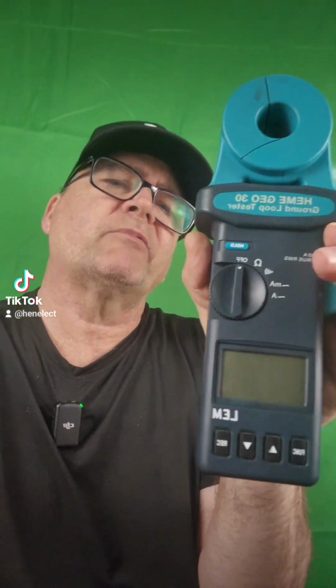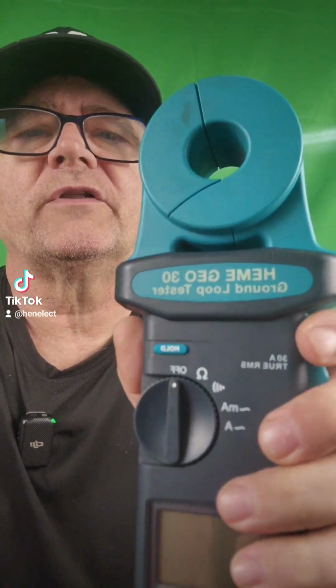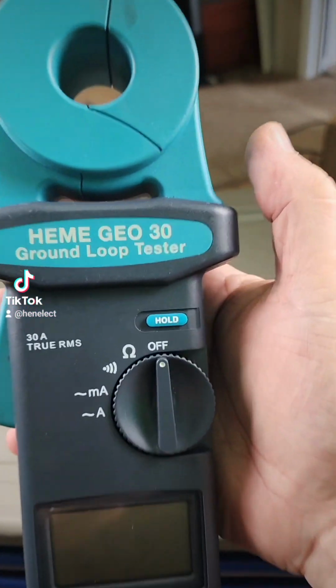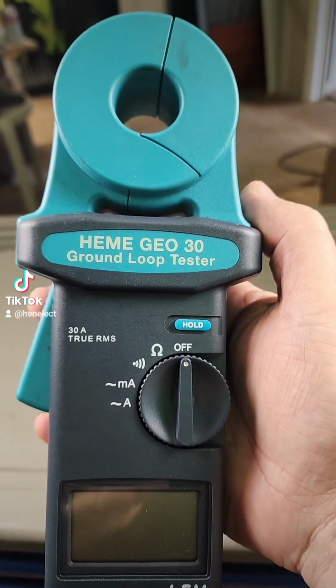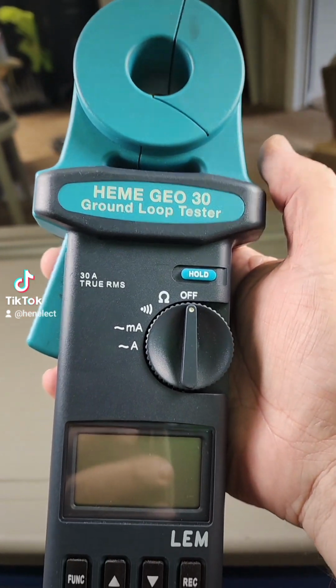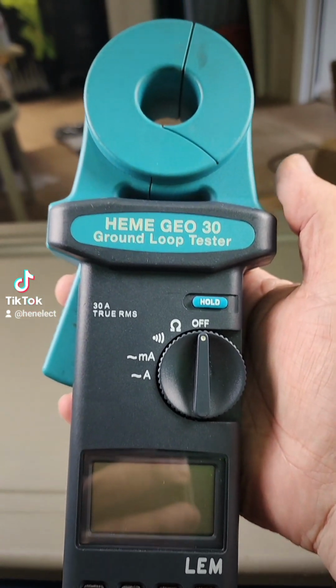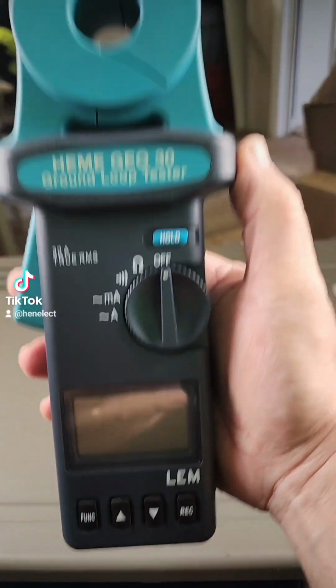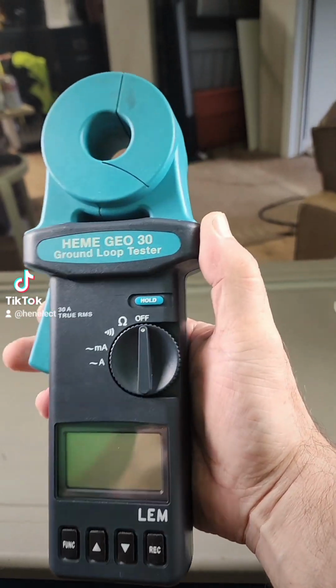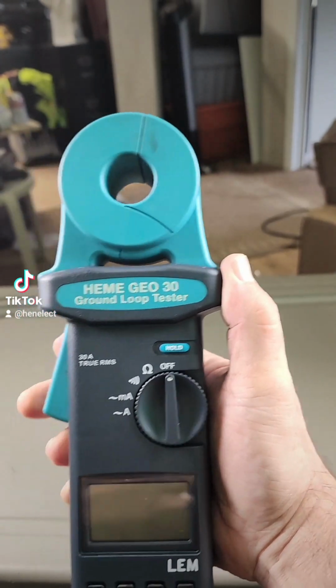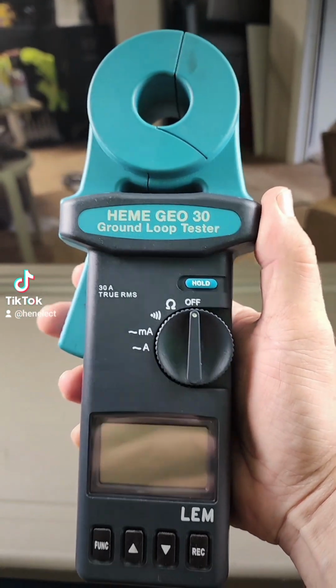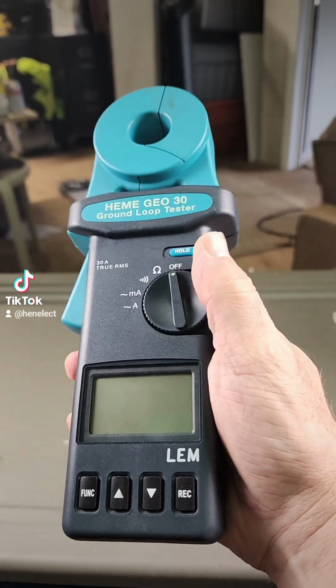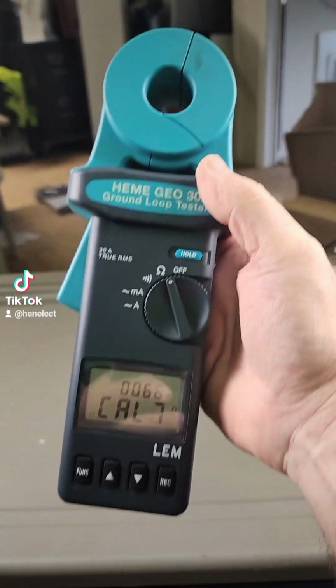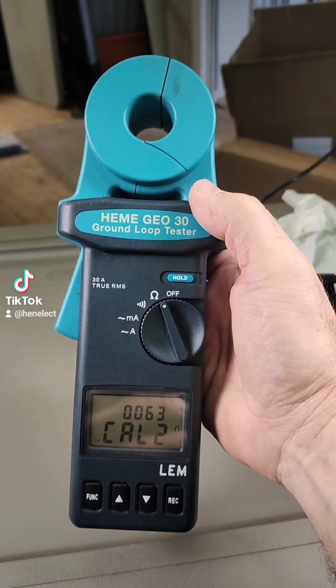How many times? Okay. You guys know what this is? You probably don't. You're going to say you do, but you probably don't. Let me flip the camera around so you can read it properly. It says a ground loop tester, by LEM, L-E-M. This is an HEME GEO 30. This device right here is about $4,000, okay? This was the only device that you could use to measure the resistance of a ground rod. Let's turn it on. But electricians weren't spending $4,000 on this.